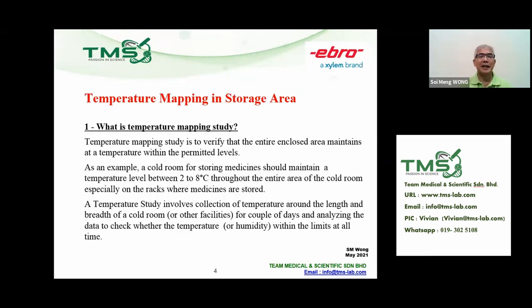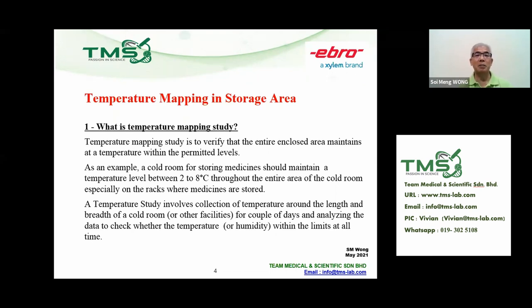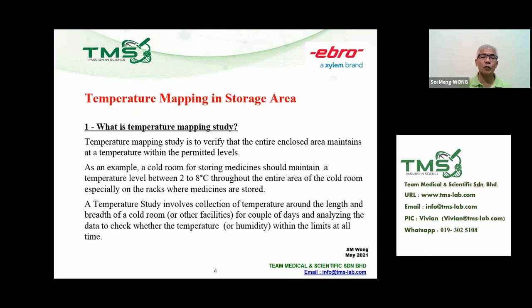First, what is temperature mapping? This term has become widely heard in the last four to six years. Temperature mapping is the study to verify that the entire enclosed area is maintained at a temperature within the permitted level. For example, a cold room for storing medicine should maintain a temperature between 2 to 8 degrees Celsius throughout the entire area, especially on the racks where medicines are stored. The study involves collecting temperature data around the length and breadth of the cold room for a couple of days and analyzing whether temperature and humidity remain within limits at all times.